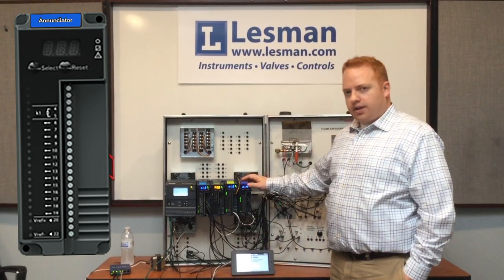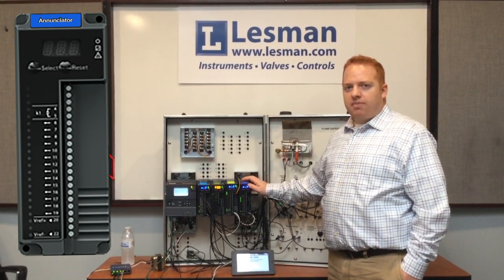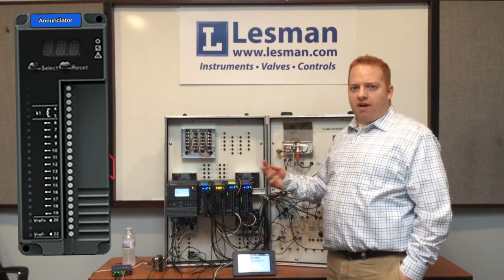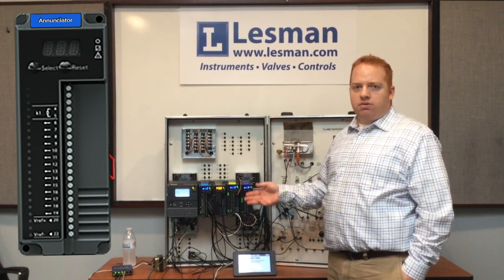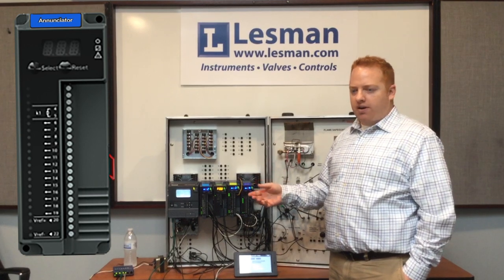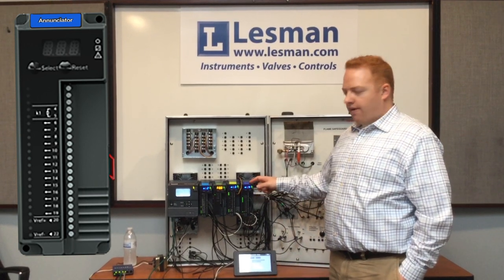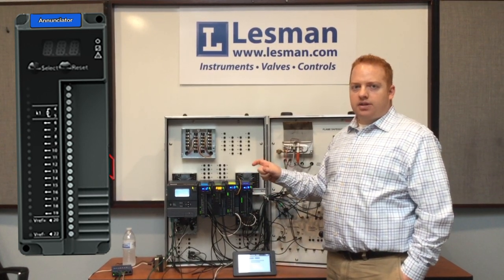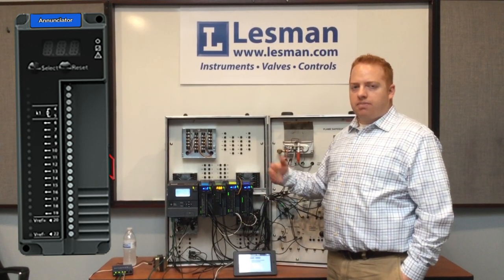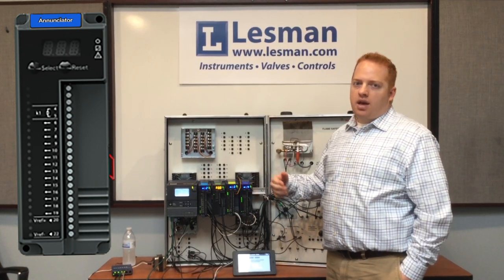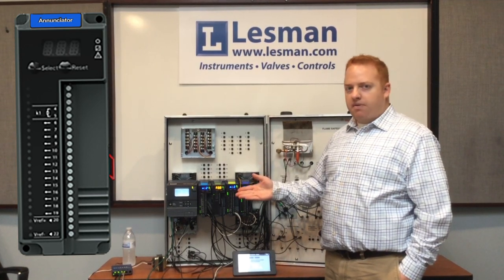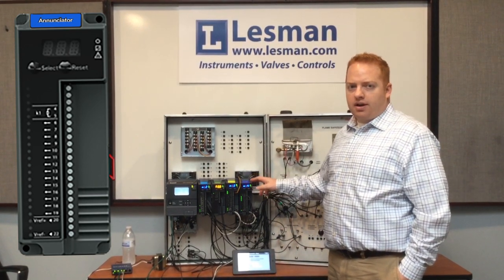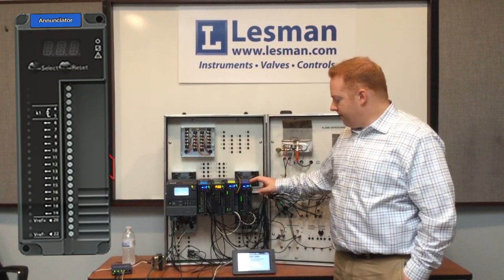The Annunciator Module can be configured as a single string, or if you have multiple fuels or if you're doing gas and oil firing, you can have a split string. So depending upon which fuel is selected, it would take a different path to prove that your analogs are made.